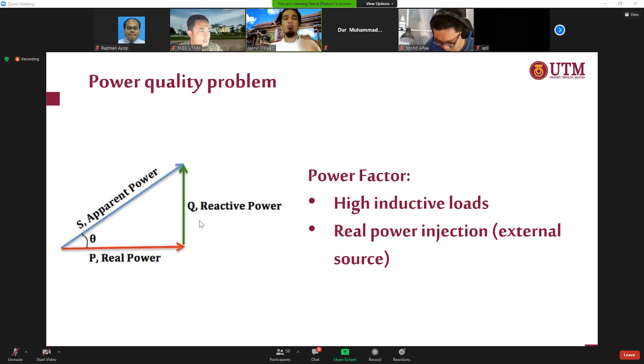All right. So we go to the last part, which is power quality issues in the grid connected PV. So this is some example of the under voltage problem. Okay, this is the real problem that we face. One of the projects in northern Malaysia. So we have a very huge PV here. Okay, this is our protection system and so on and so forth, and this is our MPPT. The distance between this MPPT and the building is nearly 300 meters. And what happened, because they wrongly sized the cable, the voltage drop is very high, which is 7%.